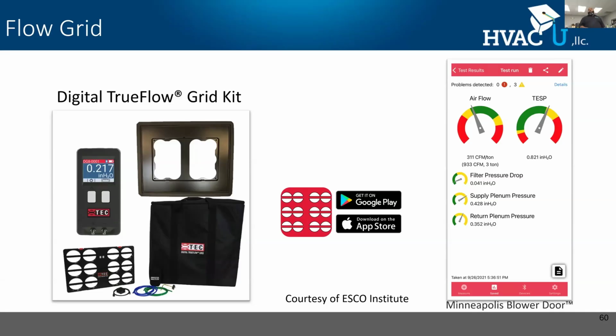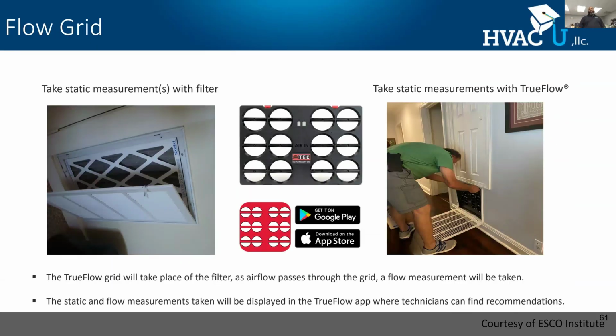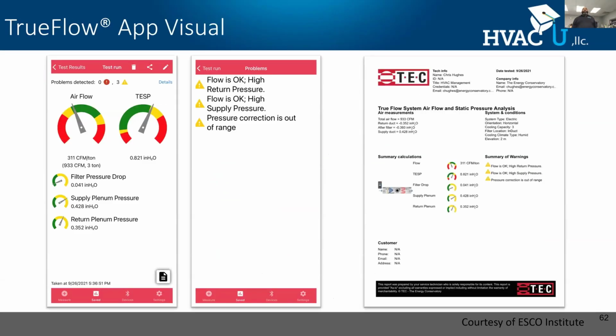And those settings can indicate and let me know if my static pressure is high, it can put that in the red. So it's an awesome communication tool to give to your clients. All right. And here's how it looks. This is the TrueFlow grid being installed into a filter grill. All right, we're taking the filter out after we take our measurements and we put the filter grill in, and we're able to calculate airflow and get static pressure. All right, here's another report, same information. We're able to see this and give this to a customer and see exactly what's going on.